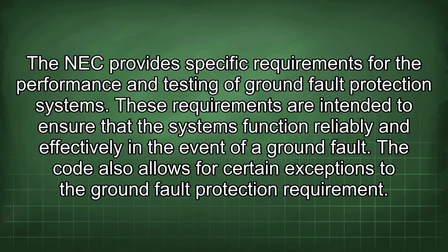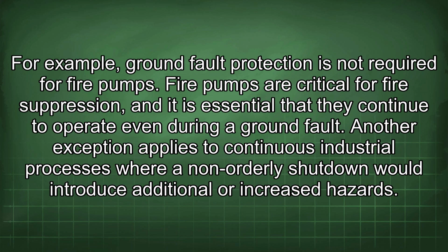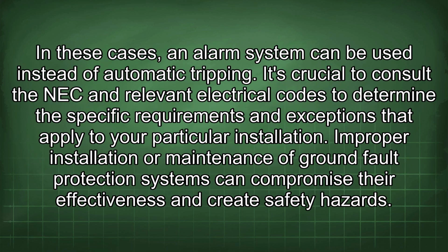The NEC provides specific requirements for the performance and testing of ground fault protection systems. These requirements are intended to ensure that the systems function reliably and effectively in the event of a ground fault. The code also allows for certain exceptions to the ground fault protection requirement. For example, ground fault protection is not required for fire pumps. Fire pumps are critical for fire suppression, and it is essential that they continue to operate even during a ground fault. Another exception applies to continuous industrial processes where a non-orderly shutdown would introduce additional or increased hazards. In these cases, an alarm system can be used instead of automatic tripping.